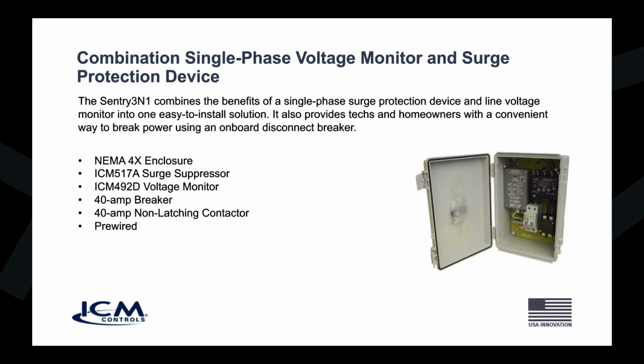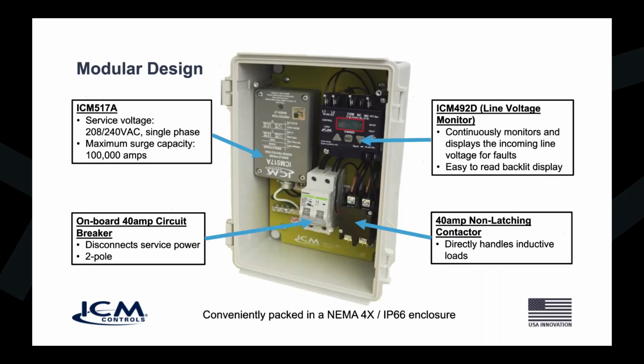So we also have a built-in 40 amp disconnect breaker, and it's all pre-wired. No messing around with having to figure out how to wire it. You literally bring your power into the disconnect switch, and your load, which is your air conditioner, connects to the contactor's load side. You're done. It's very simple. So it's an all-in-one solution for both voltage monitoring and surge protection.